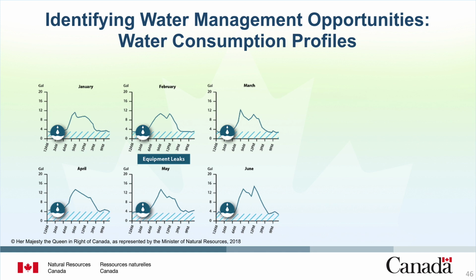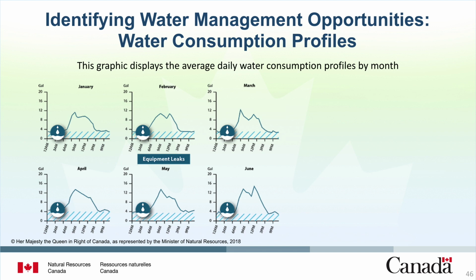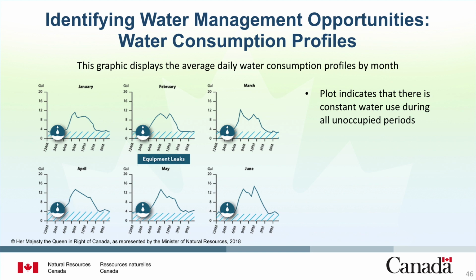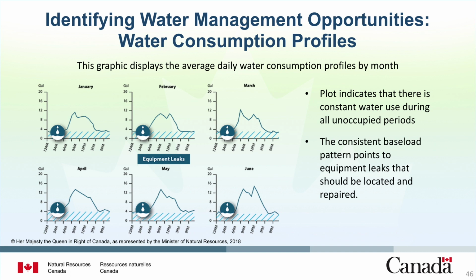Similar to how load profiles can help identify ways to improve energy management, water consumption profiles can assist to identify opportunities to reduce water consumption. This graphic displays the average daily water consumption profiles by month from January through June. The plot indicates that there is constant water use during all unoccupied periods. The consistent baseload pattern points to equipment leaks that should be located and repaired.